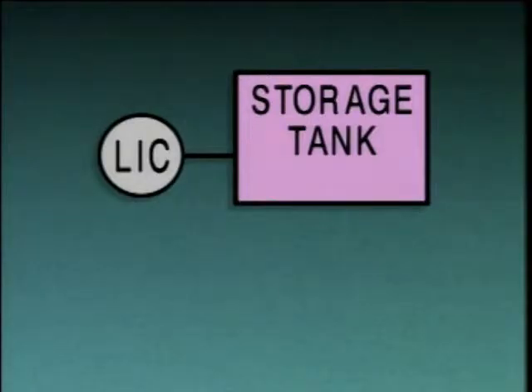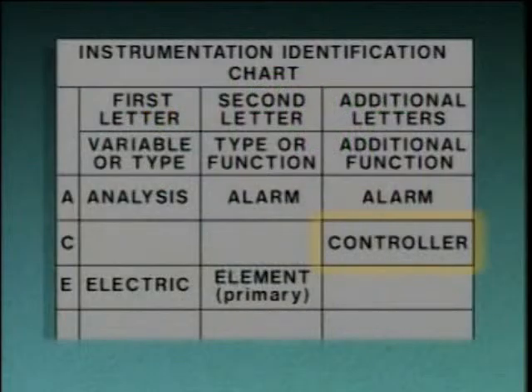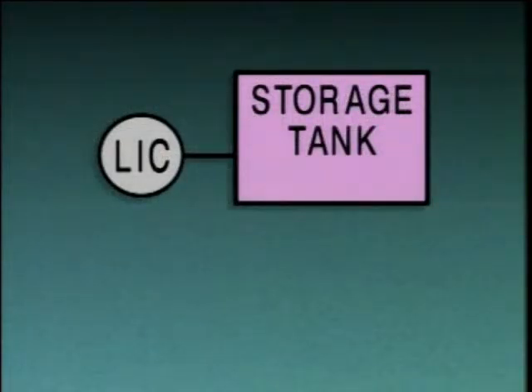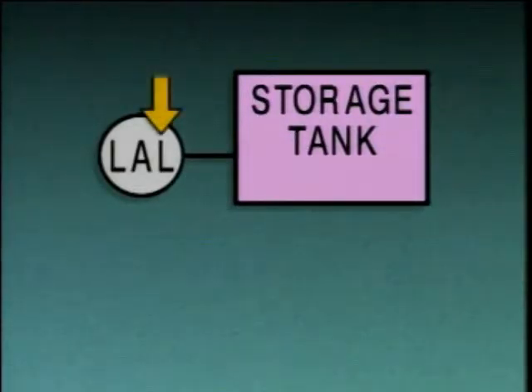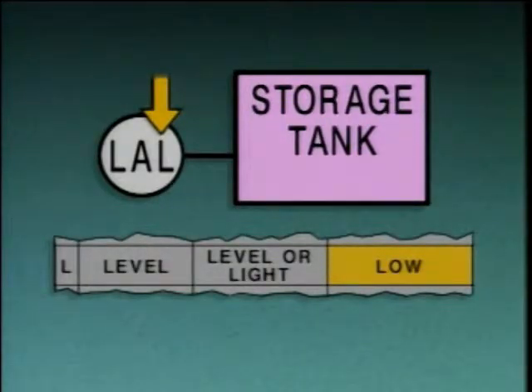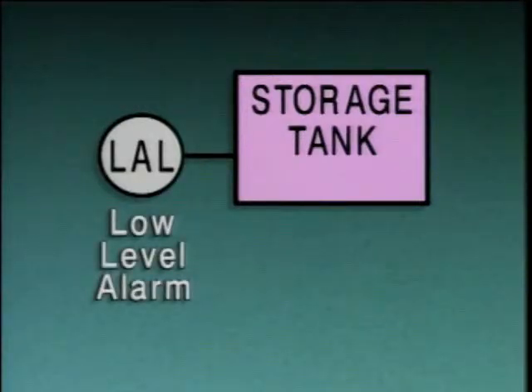Many instrument symbols contain more than two letters. This usually means that the instrument has more than one function. In this case, the third letter, C, means controller. So this is a level indicating controller. In some cases, the third letter is a modifier. For example, according to our identification chart, an L in the third position represents a low value for the process variable. The letters in the symbol stand for level, alarm, low. So this is a low-level alarm.